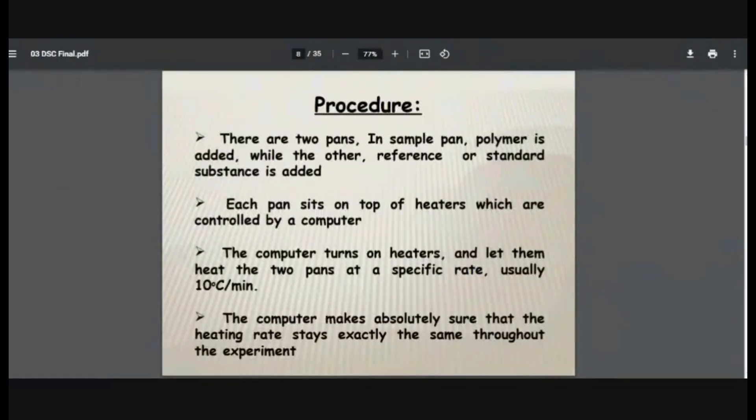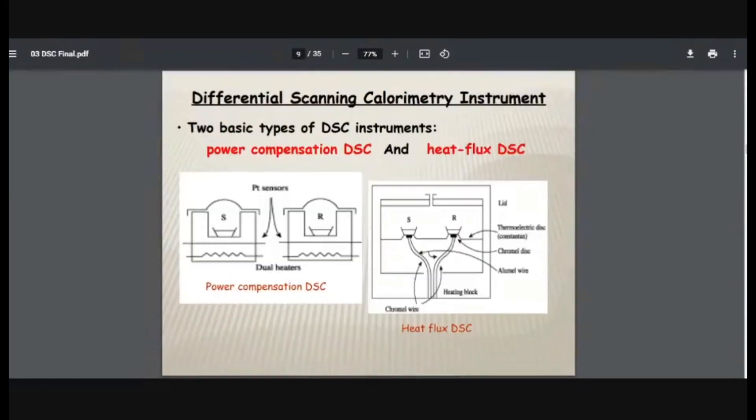Now let us see procedure in brief. There are two pans. In one sample pan, polymer is added, the sample is added, while the other reference or standard substance is added, or it may be left empty. Each pan sits on top of heaters which are controlled by your computer. So heaters are controlled by a computer. The computer turns on heaters and lets them heat the two pans on which heaters are kept - the heaters on which pans are kept. Two pans at specific rate, usually 10 degrees Celsius per minute. The computer makes absolutely sure that the heating rate stays exactly the same throughout the experiment.